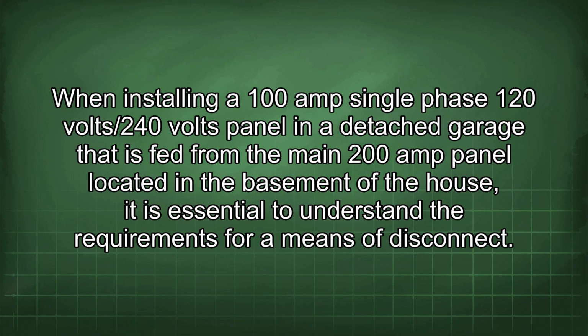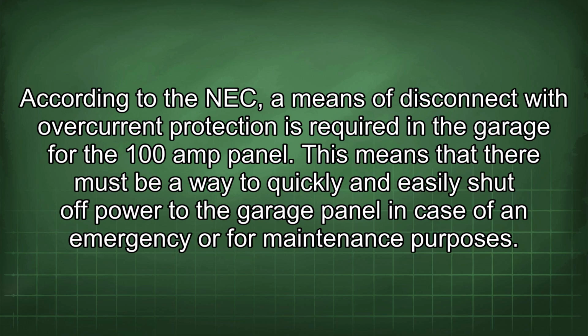When installing a 100-amp single-phase 120-volt/240-volts panel in a detached garage that is fed from the main 200-amp panel located in the basement of the house, it is essential to understand the requirements for a means of disconnect. According to the NEC, a means of disconnect with overcurrent protection is required in the garage for the 100-amp panel. This means that there must be a way to quickly and easily shut off power to the garage panel in case of an emergency or for maintenance purposes.